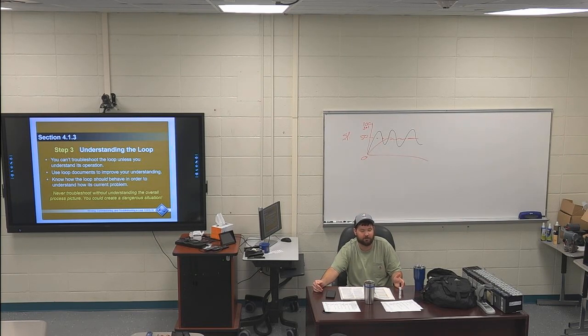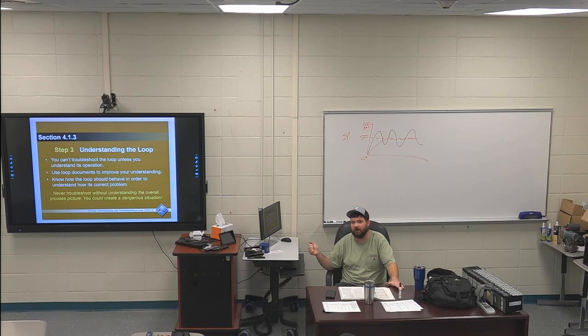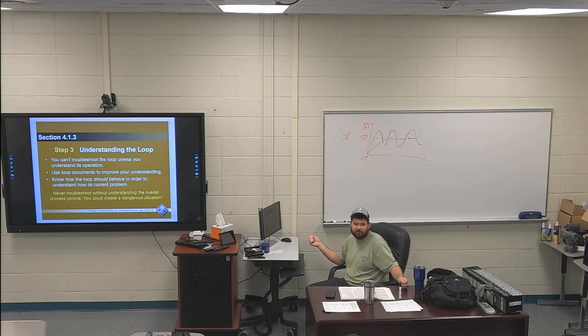Something happened where a breaker was tripped, a fuse was popped, or somebody crushed something at the other end of the line. Start at one end or the other. I've worked with a lot of maintenance people that'll just go ask them what's wrong, or be super impersonal. In our office, we could log into PLC screens on the other side of the plant, and people would try to talk to an operator on the phone instead of just getting into the PLC and seeing what's going on.